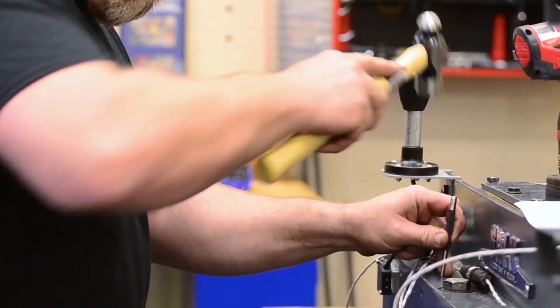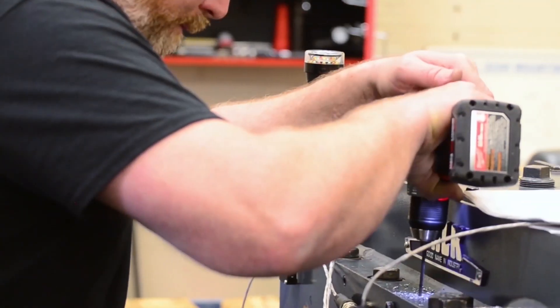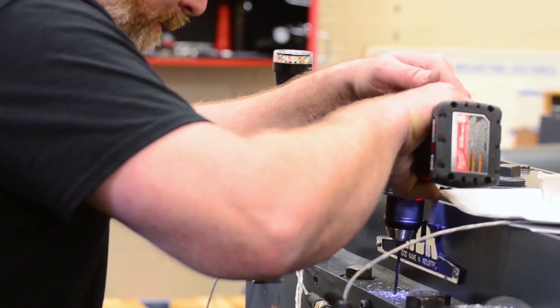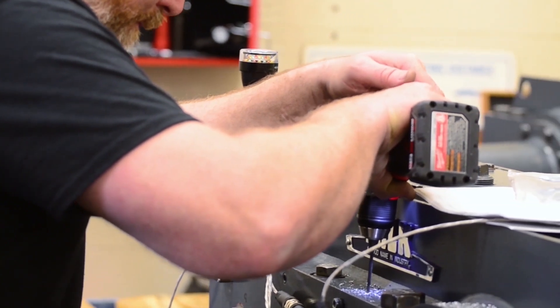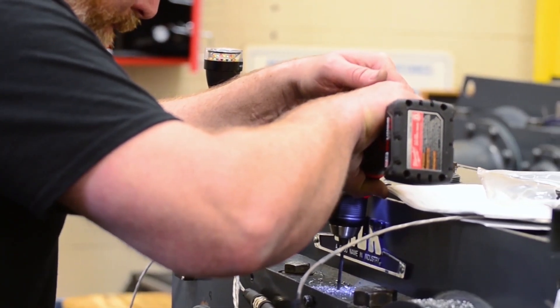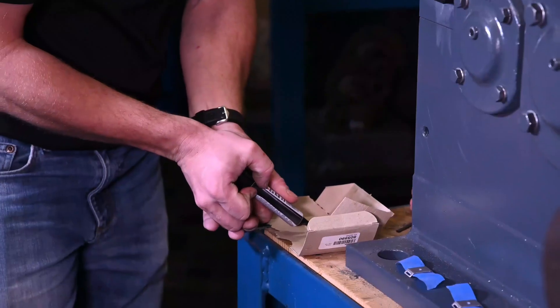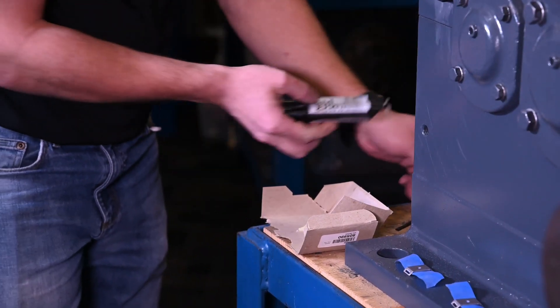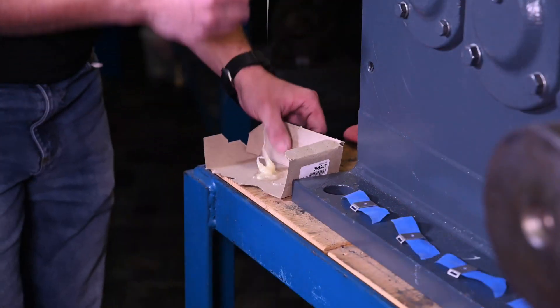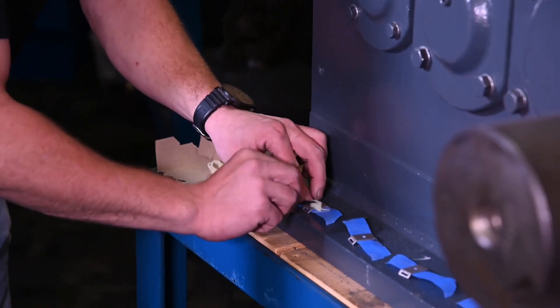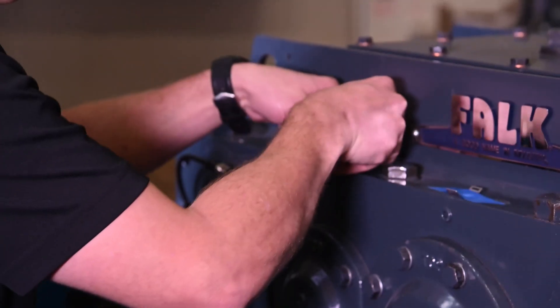For Falk gear drives, the converter clip can be drilled into the gearbox, but do not drill into the machine surfaces or through the gearbox. Alternatively, the converter can also be secured to a cable mount that is epoxied to the gear drive. Ensure that the surface is prepped and cleaned before applying the epoxy.